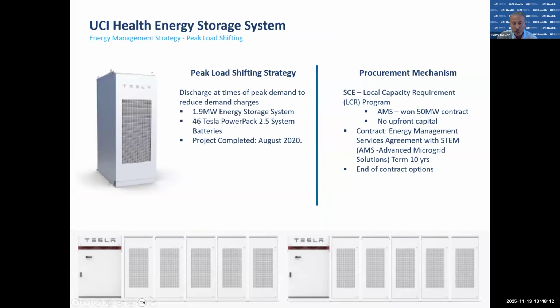The project is 1.9 megawatts. The driver was really just a peak load shifting strategy to reduce our energy bill cost through demand charge reduction. The forecasting software predicts demand spikes and switches the buildings from grid to battery power. The battery discharges during peak hours when power is expensive, and charges at night when the cost of the grid is low.